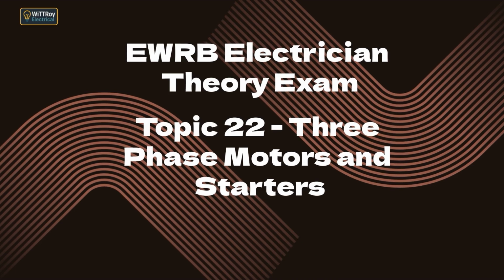Topic 22.3, Three-phase motor starters. 22.3a, describe the protection a motor starter may provide and explain how this may be achieved. A motor starter does more than just turn a motor on and off. It usually provides several types of protection. 1. Overload protection. Protects the motor from drawing too much current over time. Achieved using thermal overload relays, electronic overloads, or thermal magnetic devices. They trip when the motor heats up due to being overloaded or jammed.